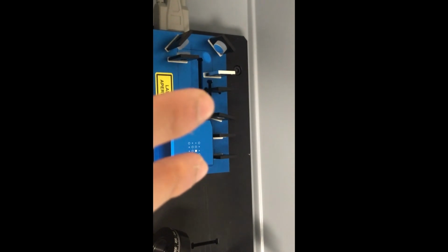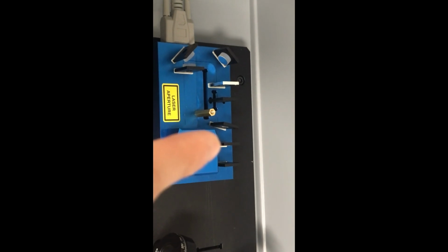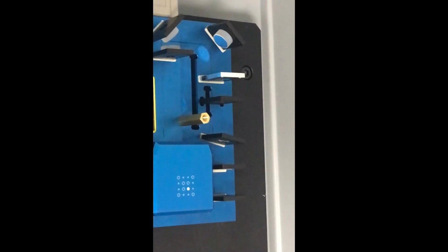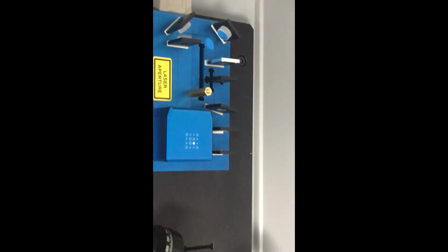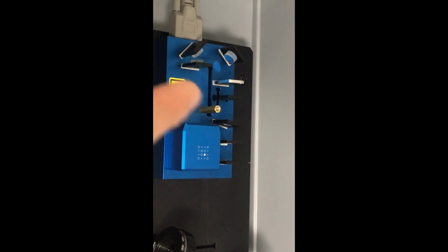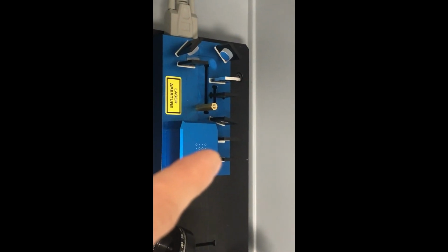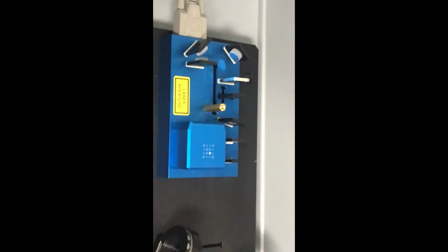So then the next thing you've got are 2 compensation plates. They're the last one and the one before the other one in the middle. The one in the middle is the barium BBO crystal. Forgot what it stands for. I've written it down in the manual. But that's essentially the nonlinear crystal where the down conversion happens. So for every pump photon that reaches that crystal at the right orientation, ensured by the wave plate, and with certain phase compensations, which is what these 2 components are. They're phase compensation crystals. So I write a little bit more about that in the manual.